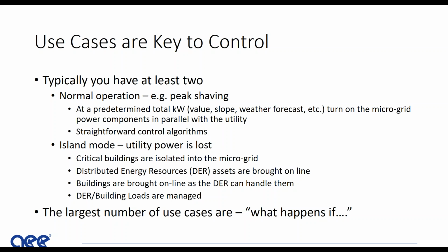Island mode is a little more interesting. Power's lost, critical buildings are isolated in the microgrid, and you bring the DER, the distributed energy resources, online. Buildings come online as the DER powers up. You don't just turn on an engine and say you're going to take 2 megawatts - you're probably not going to do that. You bring them on slowly. Once the system's at full load, can you block load? You've got to ramp it up. How do you handle that?